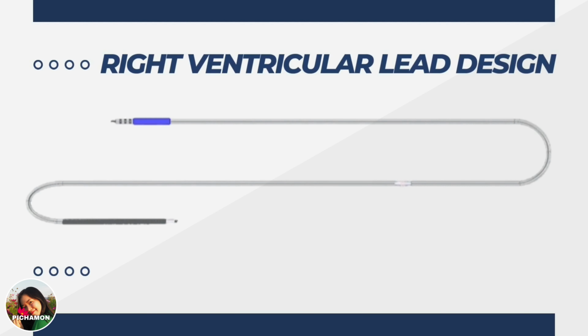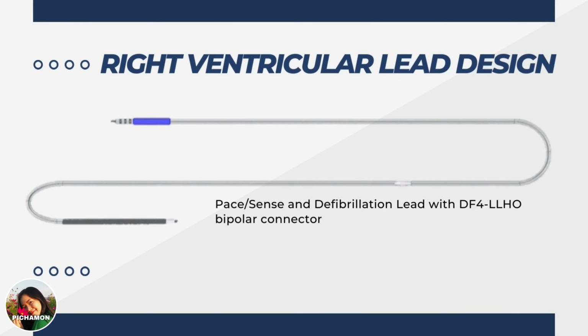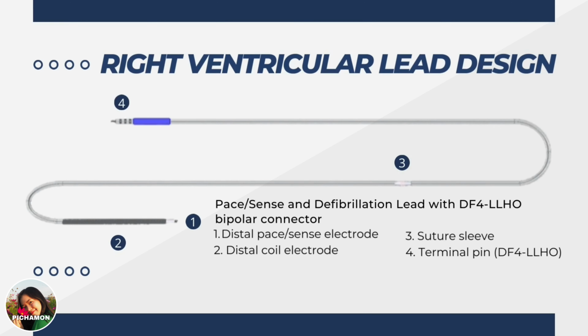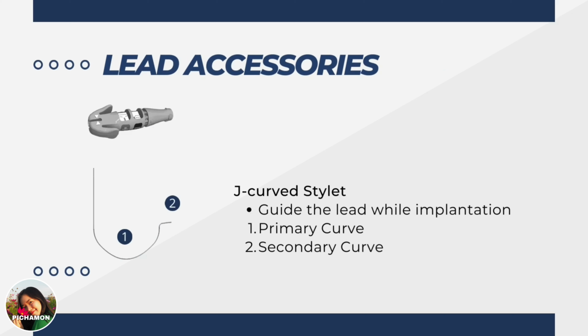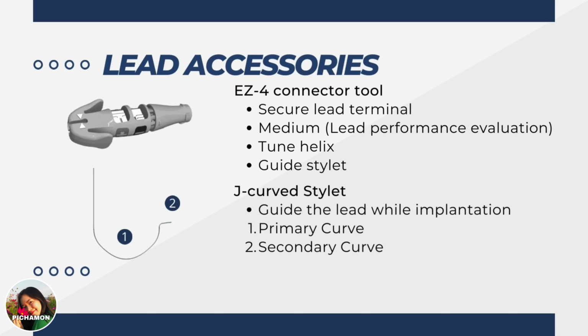The design of the right ventricular lead is based on a pacing and defibrillation lead with the DF4-LLHO bipolar connector in a single coil model. The coil electrode acts as anode and the tip electrode acts as cathode to perform sensing and defibrillating shock. The fixation helix is located at the tip electrode. For lead accessory, the first one is a lead cap design based on the EZ-4 connector tool, used to secure the lead terminal, act as a medium during evaluation of lead performance, tune the helix, and guide the stylet into the lead. The second one is a J-curve stylet, used to guide the lead.